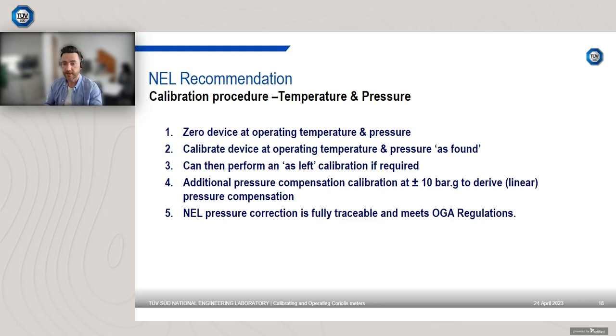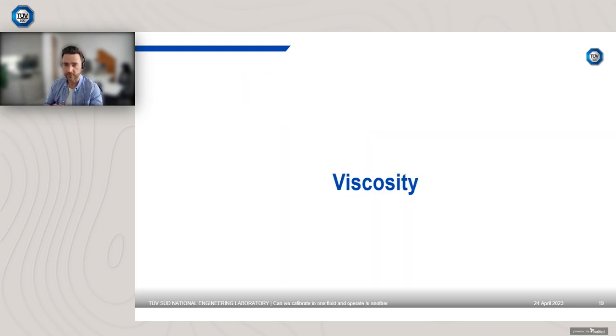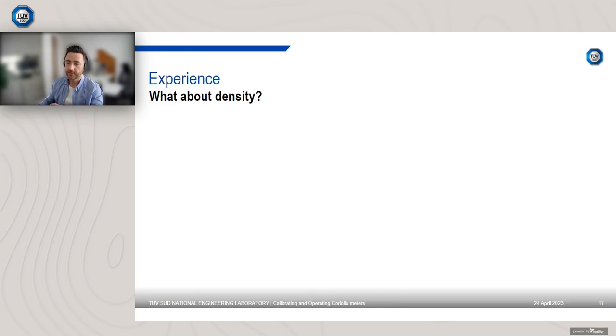The NEL pressure correction is then fully traceable and meets what we're calling the Oil and Gas Authority regulations. It's now the North Sea Transition Authority, so this is the regulations for operating in the UK North Sea. Now, if I touch upon the pressure one more time, temperature is corrected by the RTD on board, however, pressure isn't. So no Coriolis meter ships with an onboard pressure measurement. You have to supply a pressure measurement to the device, or you can use a static pressure correction.